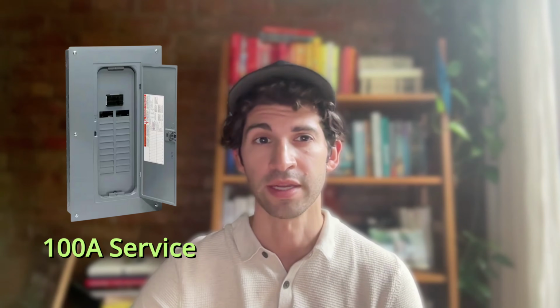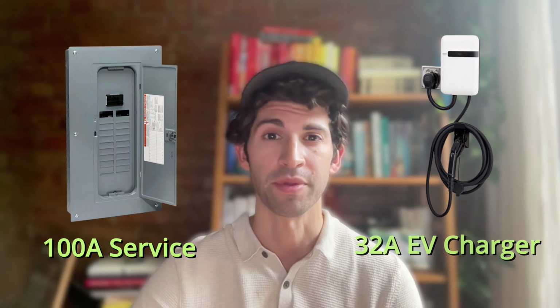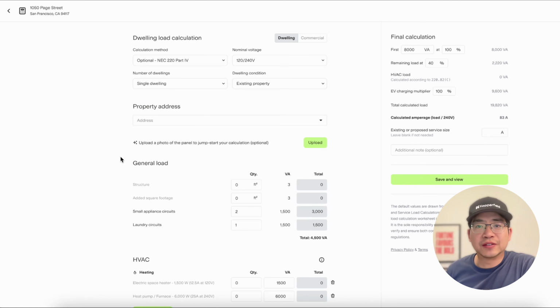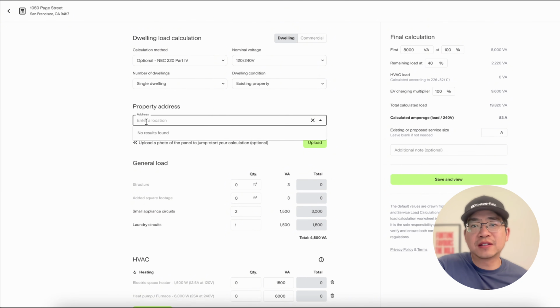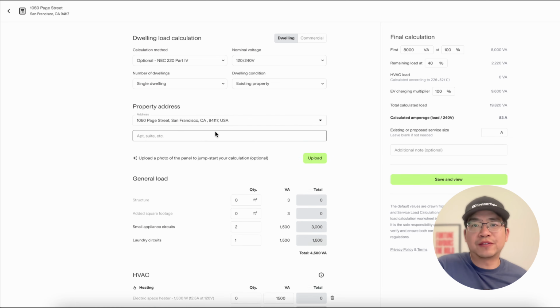The customer has a 100 amp service, and the big question is, can it handle a new 32 amp EV charger? The NEC wants you to handle the general lighting and general use receptacle loads. This is calculated at 3 volt amps per square foot. This homeowner lives in San Francisco, so I'll plug in their address, and our calculator automatically pulls in the square footage. In this case, it's just over 2,600 square feet.